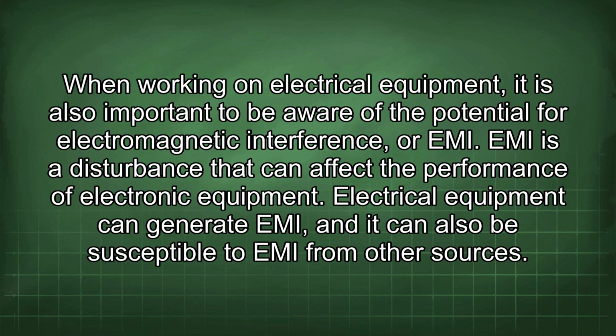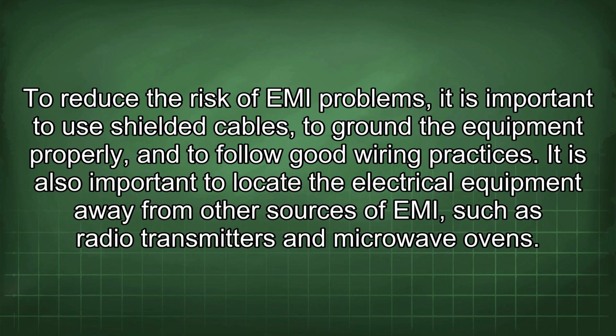When working on electrical equipment, it is also important to be aware of the potential for electromagnetic interference, or EMI. EMI is a disturbance that can affect the performance of electronic equipment. Electrical equipment can generate EMI, and it can also be susceptible to EMI from other sources. To reduce the risk of EMI problems, it is important to use shielded cables, to ground the equipment properly, and to follow good wiring practices. It is also important to locate the electrical equipment away from other sources of EMI, such as radio transmitters and microwave ovens.